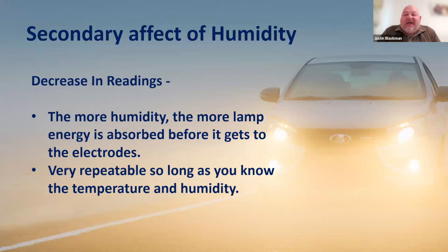However, I would like to introduce to you the secondary effect of humidity. Now, we never normally get to see this effect because we test our PID diligently with calibration gas, and calibration gas is completely dry. No moisture in the isobutylene and air mixture in our calibration gas.